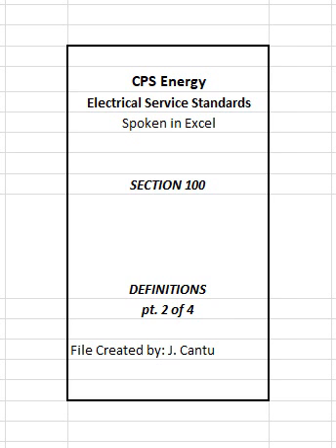Meter, revenue. Kilowatt-hour or kilowatt-hour/kW, the device or any auxiliary equipment installed by CPS Energy to measure electric energy taken by the customer. Note: meters are classified as either single-phase or three-phase and are either self-contained or transformer-rated. Self-contained meters operate directly from the service voltage and load current. Transformer-rated meters require current transformers, CTs, or voltage transformers, VTs, or both, to reduce the service current or voltage when they are beyond the measuring capacity of self-contained meters.